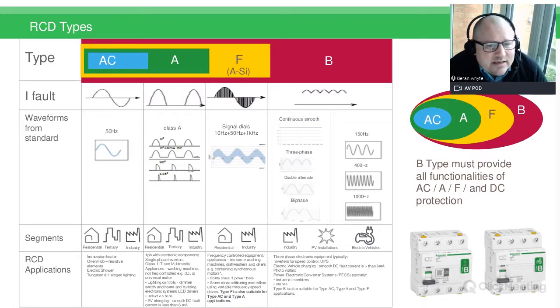Who would have thought 30 years ago we'd be having LED lighting in a home? And who'd have thought 20 years ago we'd have inverters in the home? That's what we're seeing in certain domestic appliances, washing machines, tumble dryers. Although the inverter gives us better control and efficiency, it does have the effect of pushing DC currents back onto the network. So the Type F is there for higher DC currents.